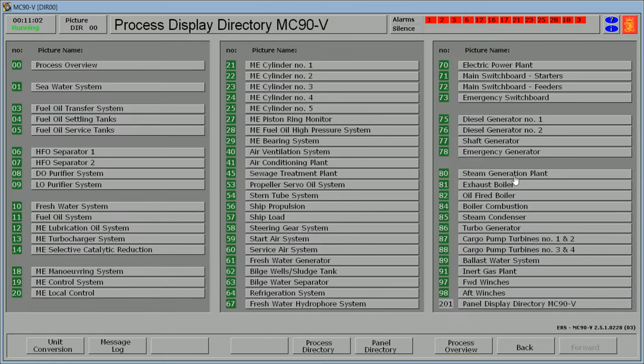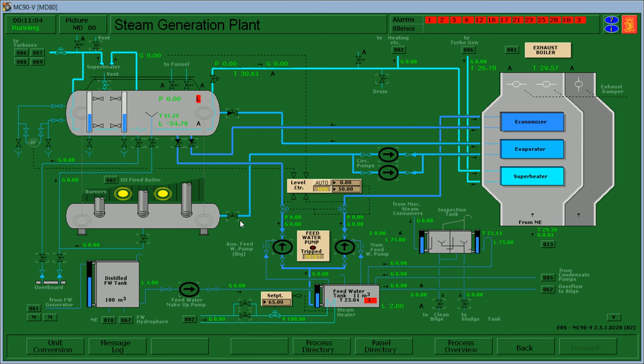We proceed to steam generation plant. Open the circulation outlet valve and the inlet and start one circulation pump. Open main feed water discharge valve. Set the manual to 0. Turn on the main feed water pump and set level control to auto.